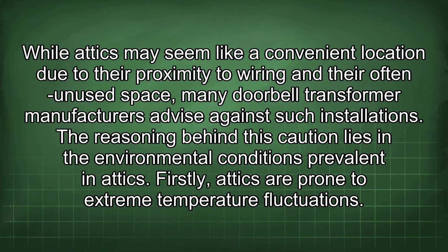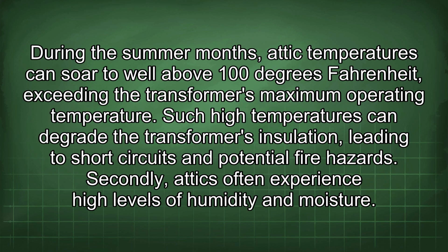Firstly, attics are prone to extreme temperature fluctuations. During the summer months, attic temperatures can soar to well above 100 degrees Fahrenheit, exceeding the transformer's maximum operating temperature. Such high temperatures can degrade the transformer's insulation, leading to short circuits and potential fire hazards.